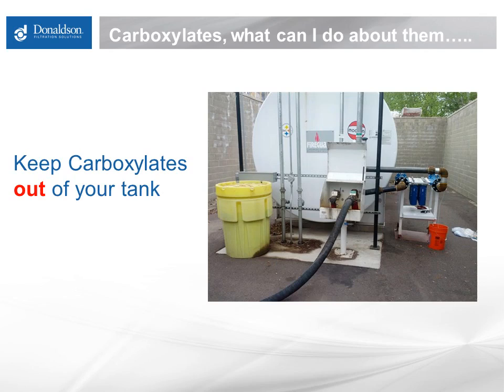If you can't really prevent them from being delivered to you, the best bet is to prevent them from entering your fuel tank. High efficiency inlet filtration on your bulk storage tanks will prevent insoluble carboxylates in the fuel from getting into your tank in the first place. Keep in mind, carboxylates in the fuel can rapidly plug inlet filtration as well, but the problem will stay out of your tank and, more importantly, out of your equipment.